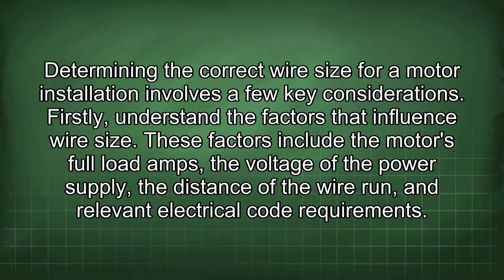Determining the correct wire size for a motor installation involves a few key considerations. Firstly, understand the factors that influence wire size. These factors include the motor's full load amps, the voltage of the power supply, the distance of the wire run, and relevant electrical code requirements.